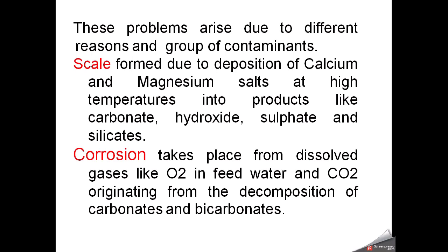Second, very important, is corrosion. Corrosion takes place due to the presence of dissolved gases like oxygen in feed water, or carbon dioxide, which is produced during the decomposition of carbonates and bicarbonates. This carbon dioxide is present in the water circuit and causes the problem of corrosion.